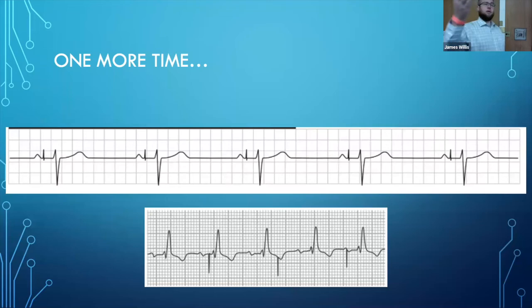So the pacemaker is working. The pacemaker is firing, but the problem is that it's firing at the wrong time. The pacemaker is basically failing to detect the correct electrical activity. So what's going on here is it's called undersensing. So we're not sensing enough in this situation. Pacemaker might not be in the right spot. The lead may be broken.